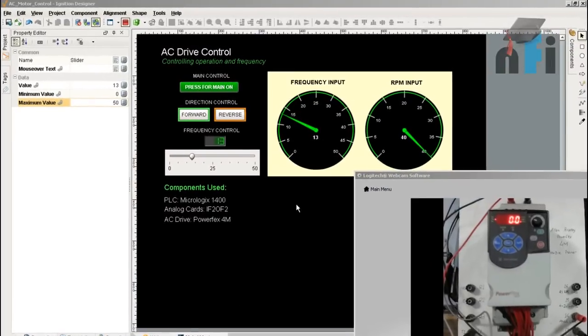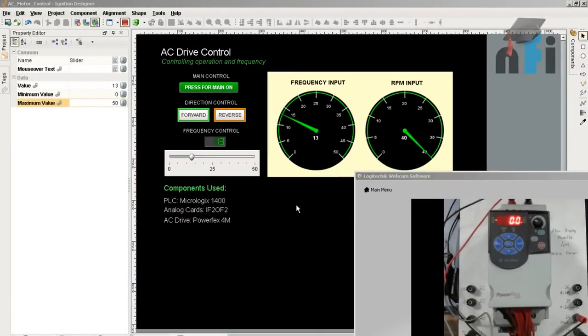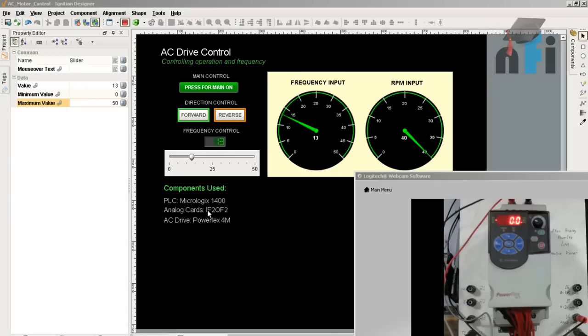In this video, we are going to talk about AC drive control, controlling operation and frequency using a SCADA screen. The PLC we are using is Micrologix 1400 which has an analog card IF2OF2 as an external module, and the drive is PowerFlex 4M. We have to control the start-stop operation and frequency of this drive using the SCADA screen.